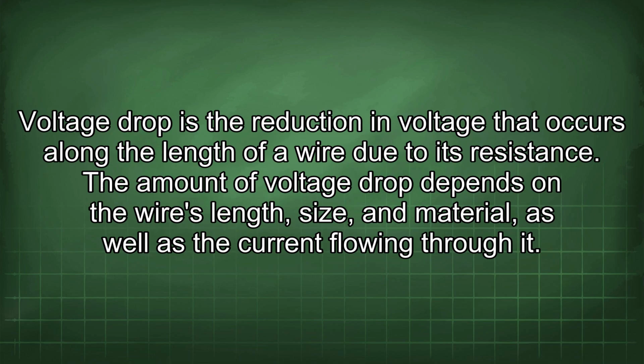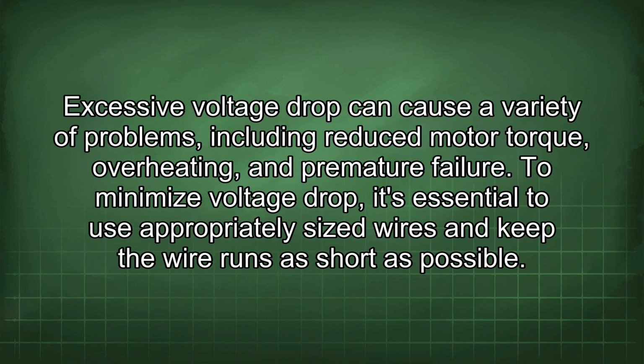Voltage drop is the reduction in voltage that occurs along the length of a wire due to its resistance. The amount of voltage drop depends on the wire's length, size, and material, as well as the current flowing through it. Excessive voltage drop can cause a variety of problems, including reduced motor torque, overheating, and premature failure. To minimize voltage drop, it's essential to use appropriately sized wires and keep the wire runs as short as possible.